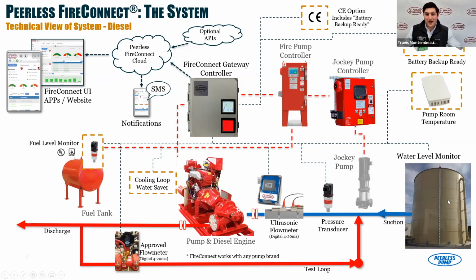You may have a water supply tank if you're not fed from a city supply. So, a lot of you in New York City, for example, have water supply tanks in the buildings. If it's diesel driven, there's a diesel fuel tank in there. And a lot of systems have an approved flow meter for running your annual flow test, being able to run it through a flow meter loop, for example. There are a lot of other components in there, but that's the crux of your pump room, the most important critical components that are in there.